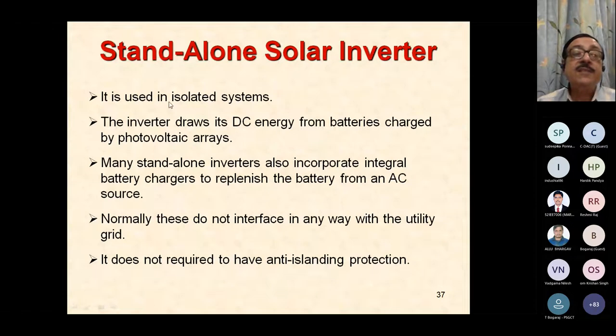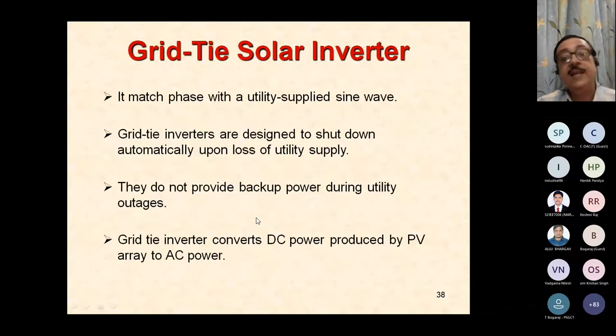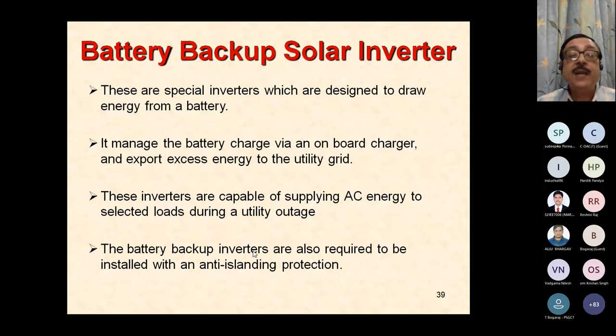The standalone solar inverter system is used in isolated systems. The inverter draws its DC energy from batteries which are charged from the photovoltaic arrays. They can also have integral chargers to operate from an AC source if the source is available. They do not interface in any way with the utility. It does not have any requirement for anti-islanding protection because it's not connected to the grid. Grid tie matches phase with a utility supplied sine wave, exactly what I have said. They do not provide power backup, and the grid tie inverter converts DC power produced by the panel to AC power. And here, for the battery backup, you have an addition of the battery system to it.